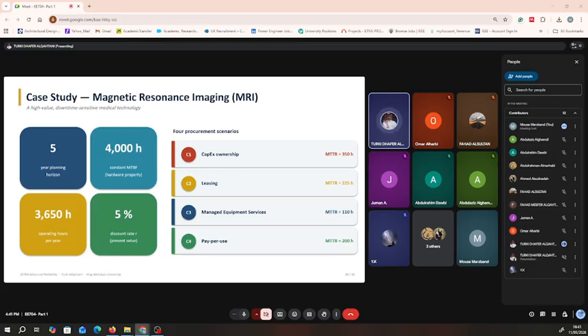For the case study, I selected an MRI machine. I chose this technology because it's high value, maintenance intensive, and very sensitive to downtime. The planning horizon is 5 years. Mean time between failure is kept constant at 4,000 hours because it's treated as a hardware property. Annual operating time averages 3,650 hours, and the discount rate is 5%. Then I compared four scenarios.